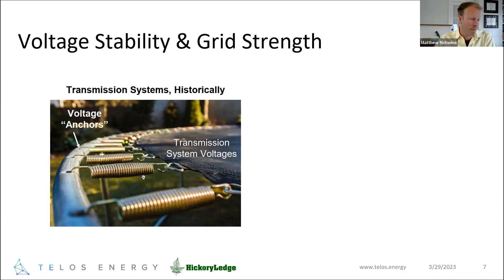As we proceed to a weaker system, weakening grids, conventionally that's meant displacing synchronous machines, retiring or decommitting them, which looks like disconnecting our trampoline in places from its voltage anchor. If you apply a load to the transmission system, you expect some voltage drop, some deflection in the trampoline. When you disconnect more of these machines, the springs from the metal rail, you'd expect more deflection in the trampoline as well.